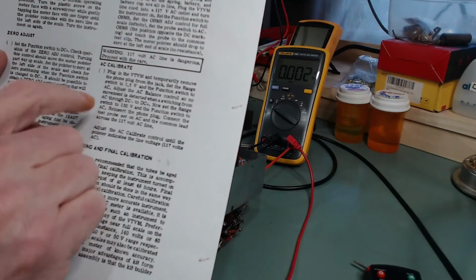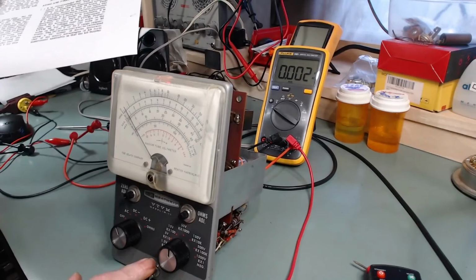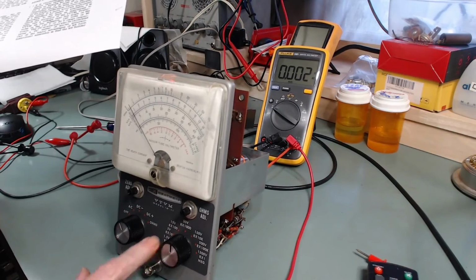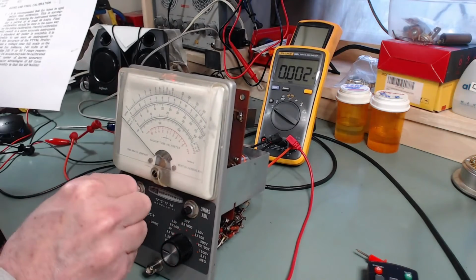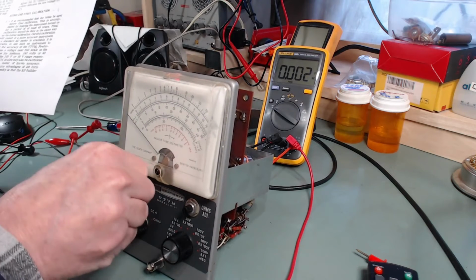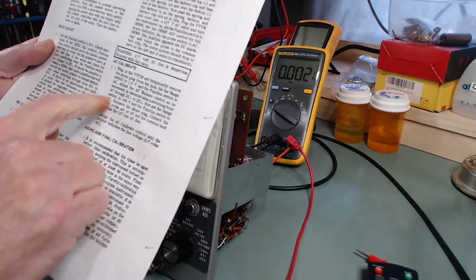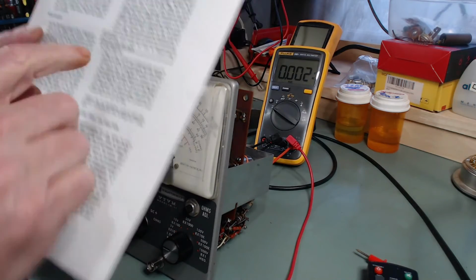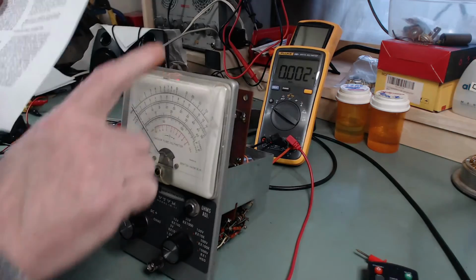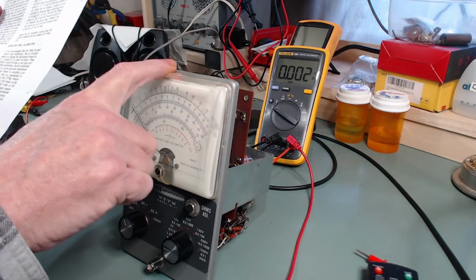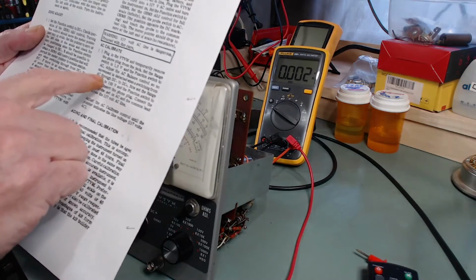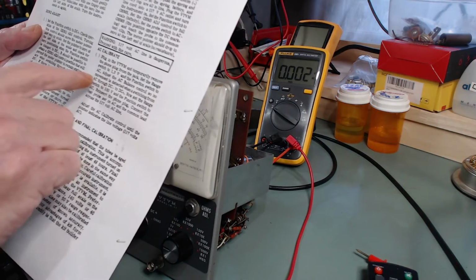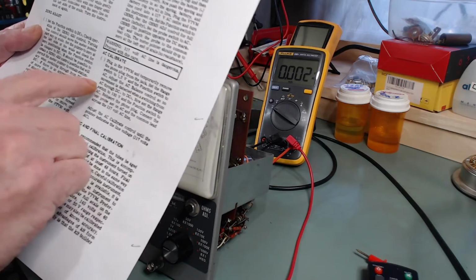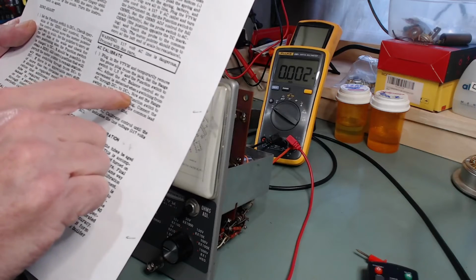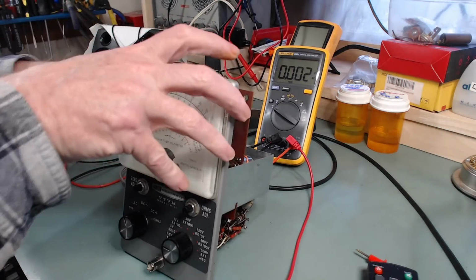So the first part basically says plug it in, turn it on, and disconnect the main front jack, which is this right here. So this is disconnected. Set the range switch to 1.5 volts. Zero the meter out, and the function switch to AC, which it is. Also, this has been on for several hours now, so it's nice and toasty warm. Adjust the AC balance control so that no movement is detected when switching from AC through DC minus to DC plus. So that's what we'll do right now.